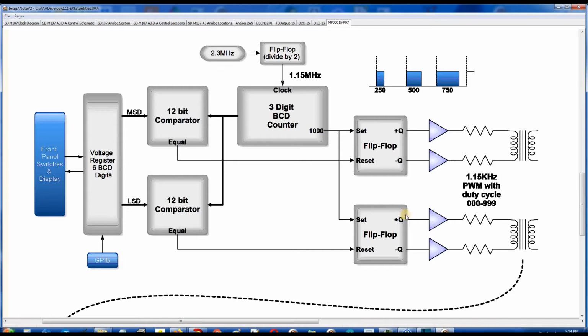Same again for the least significant. Now, those 2 outputs from the flip-flop, Q is high when that's high, and Q minus is high when it's not, so they're always opposite. It goes through an amplifier to drive the pulse transformer primary. So when it's set, the current's going one way, and when it resets, the current goes the other way. And that switching from set to reset and back again, these edges, when it goes up, when it goes down, provides a little pulse to the other side of the isolation barrier.